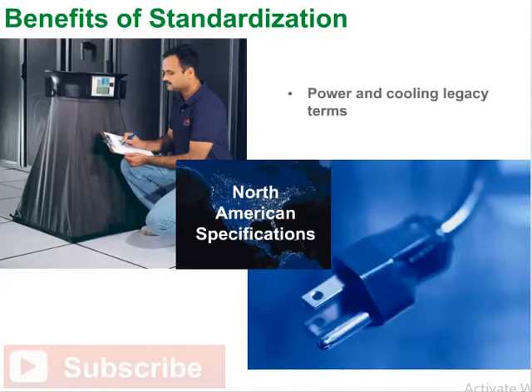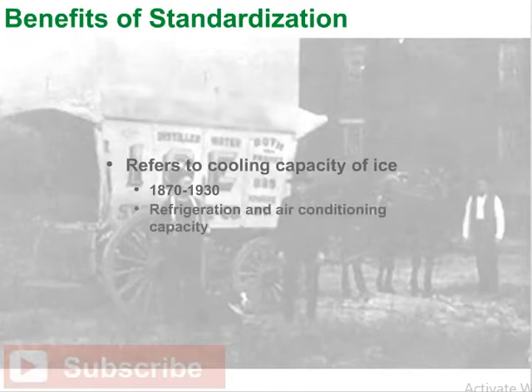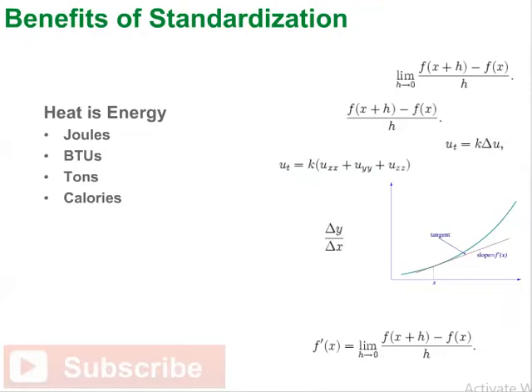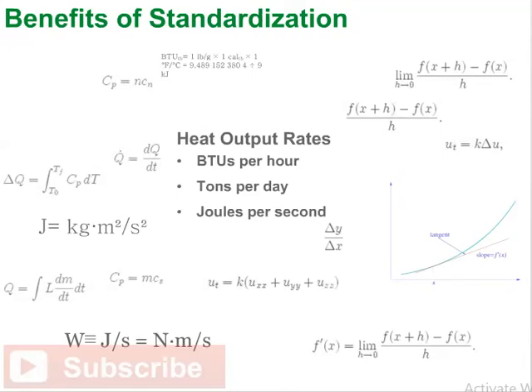In North America, specifications for power and cooling capacity are still often provided in the legacy BTU and tons terms. The term 'tons' refers to the cooling capacity of ice — a relic of the period from 1870 to 1930 when refrigeration capacity was provided by daily delivery of ice blocks. Other parts of the world use specifications such as joules or calories in addition to BTUs and tons. Common measures of heat output rate are BTUs per hour, tons per day, and joules per second.